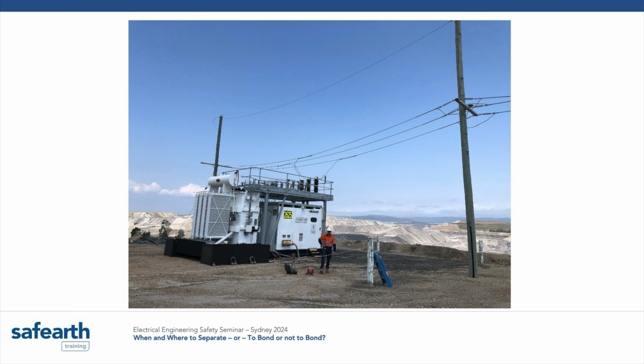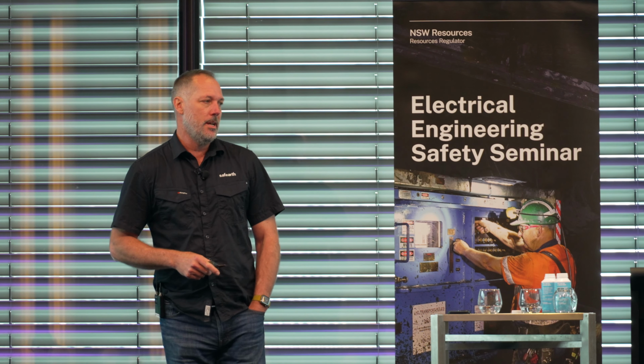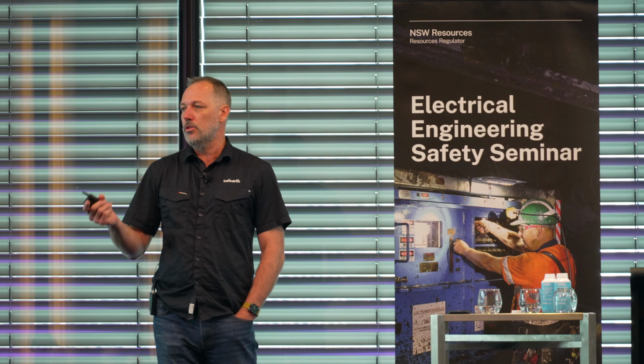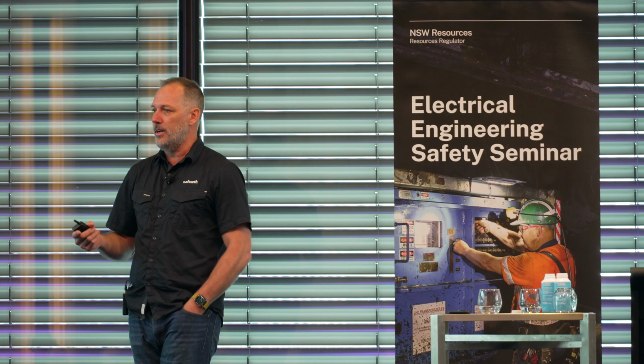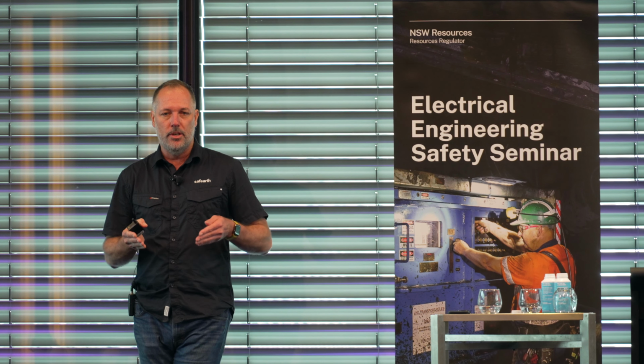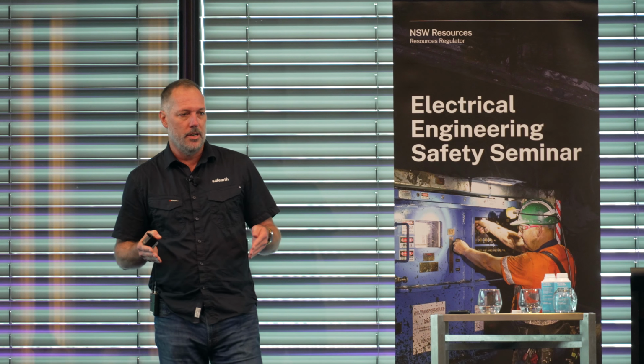In this instance, without the earth wire connected, obviously it won't return fault current in the same way, but it still will. And I'll tell you what else will happen. If that earth wire runs all the way back to its source, and even if it's, let's say, a 200 amp fault limited system, 200 amps is still pretty reasonable current, that'll produce a voltage on that earth wire, and because it's unearthed at that point, it'll create what I call a coupling factor change or an end of line effect, which will put a really, really big voltage on that earth wire termination at the ground.